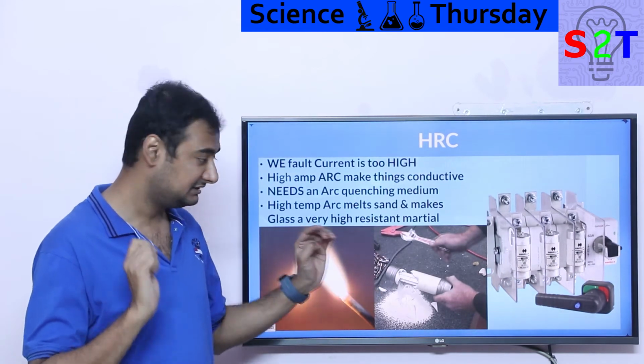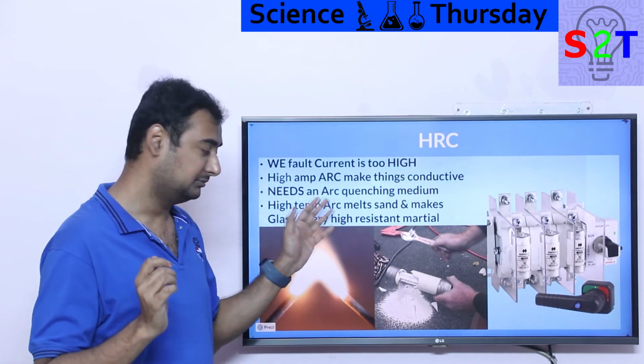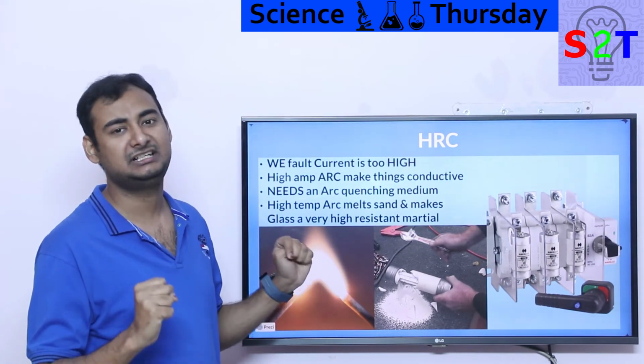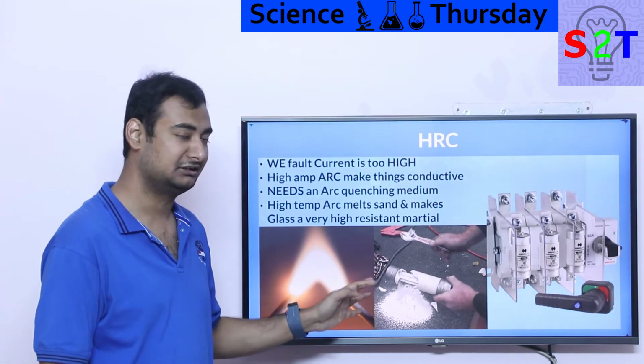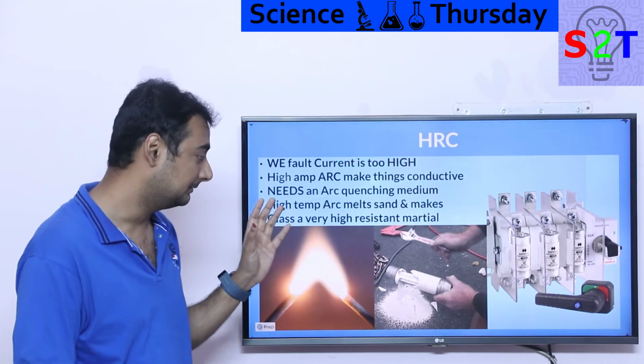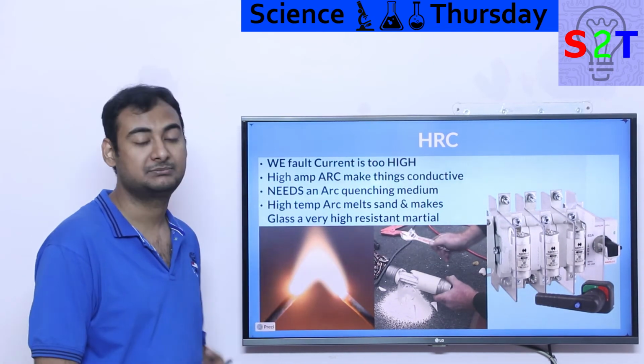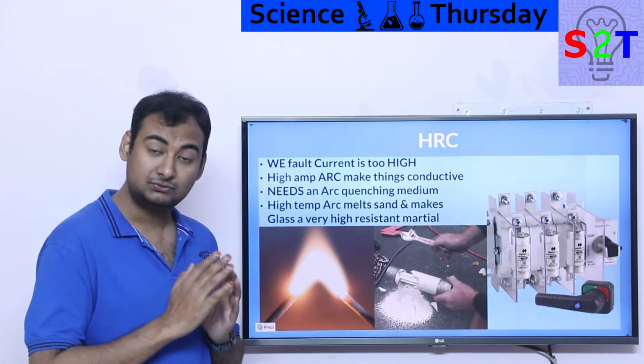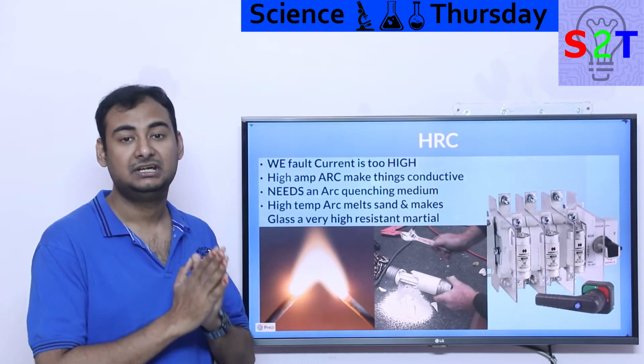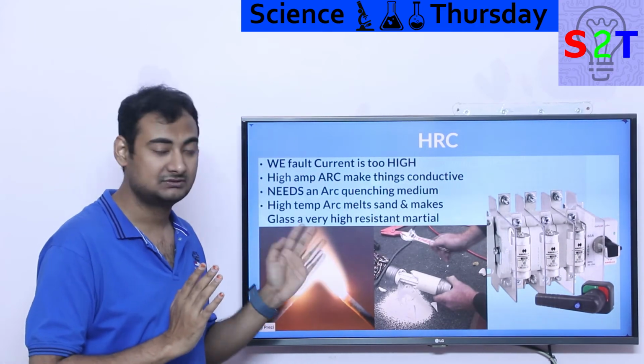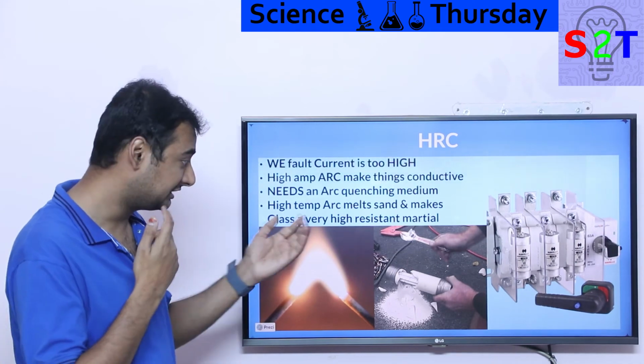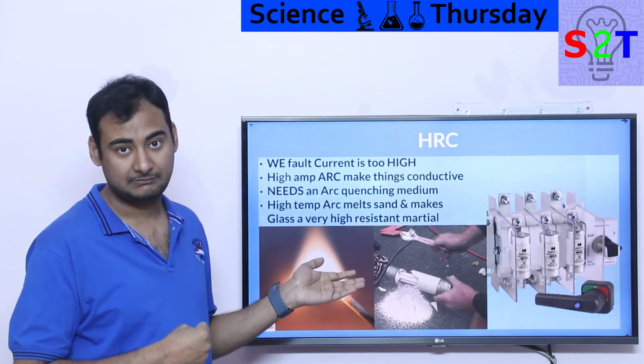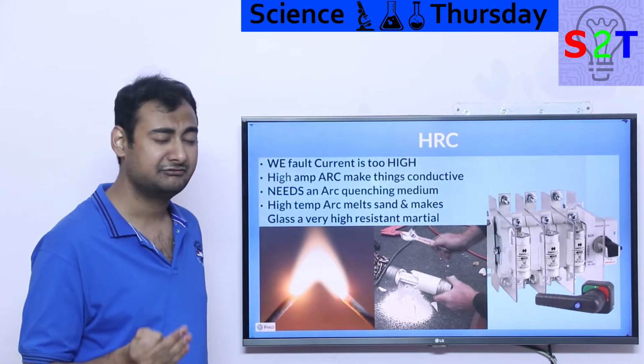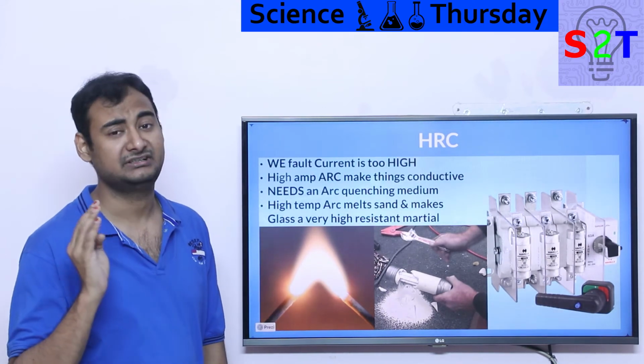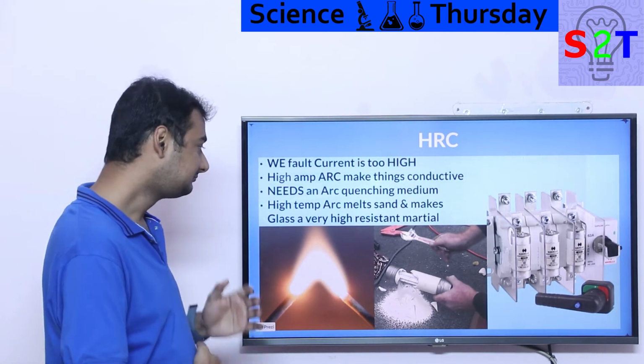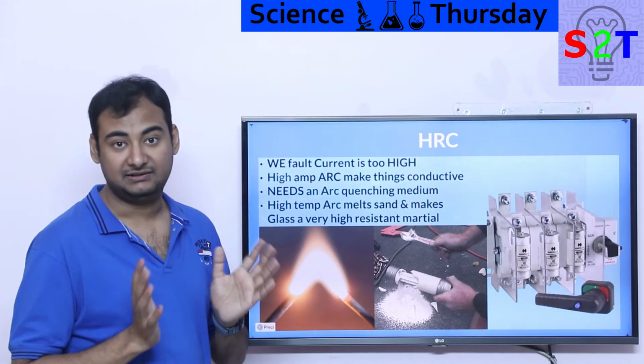These things are almost like, once they go open, electricity has to do some idiotically high power stuff to jump across, because they cannot. Inherently they are designed in such a way. And because of the reaction speed, generally they are preferred over MCBs. So you could have an MCB and fuses also, but generally if you are talking about something very severe, this will trip before the MCB does. And you generally want this also simply because your fuses are replaceable but your equipment is not, and they can have very fast response times, like 4 milliseconds or even faster than that. So in those sorts of scenarios, these materials save people's lives.